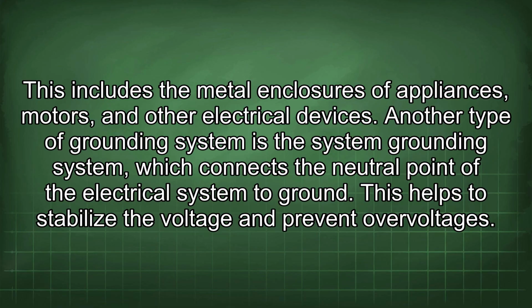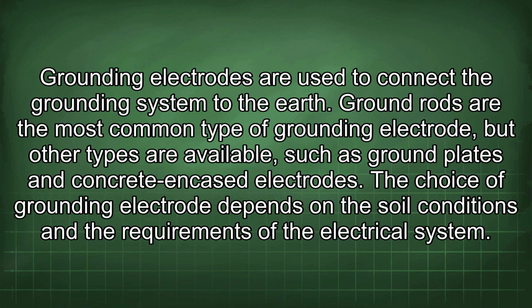This helps to stabilize the voltage and prevent overvoltages. Grounding electrodes are used to connect the grounding system to the earth. Ground rods are the most common type of grounding electrode, but other types are available, such as ground plates and concrete-encased electrodes. The choice of grounding electrode depends on the soil conditions and the requirements of the electrical system.